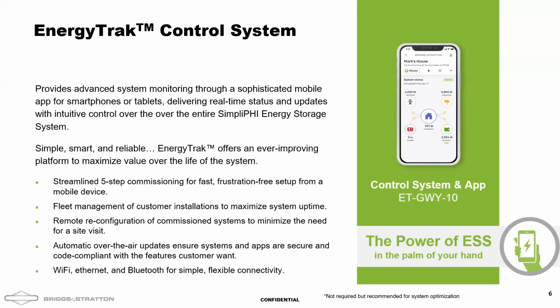And beyond that, you can even reconfigure the system remotely and do quite a bit of troubleshooting just through the app. I mean, you're going to get push notifications when there's a warning or a fault, and you can simply go into the app and maybe change a setting or two that are causing that fault or warning without even visiting the site. Another thing limiting the amount of time you have to spend visiting the site is our ability to do over-the-air firmware updates on both the batteries and inverter.